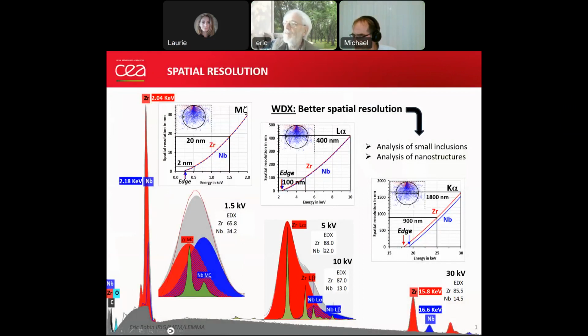Yes. In fact, this is just the problem of measuring niobium in zirconium materials. So the problem was to measure the concentration. Of course, by EDX, you have a strong convolution between zirconium and niobium. Of course, it's possible to perform some deconvolution. Here we see that it's possible to work at high voltage, but as I explained, you still have the problem that at high voltage, the spatial resolution is very, very bad. If you use 5 kilovolts, the spatial resolution is better.